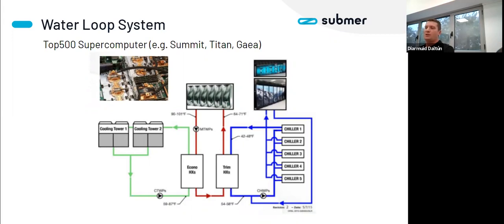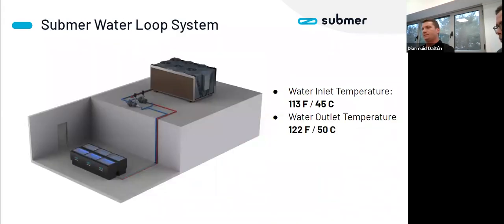And there's a combination of obviously shaving the peaks with chilled water, as can be shown here. All these diagrams are public information from the Oak Ridge labs and so on. So, yeah. But you're saying that we would use only, let's say, the passive cooling as such, rather than having any compressors or chillers. Absolutely. So we would take a much simpler approach with less infrastructure, which essentially also means less space on the outside and the inside of the data center, because that's also something to be considered.